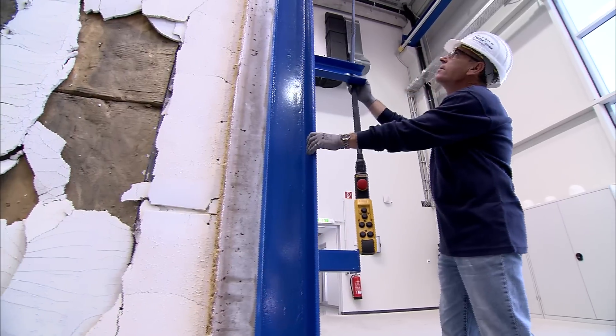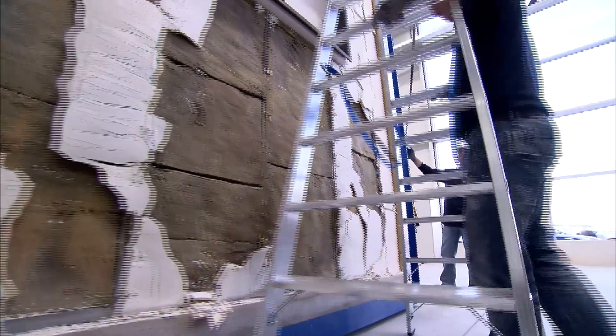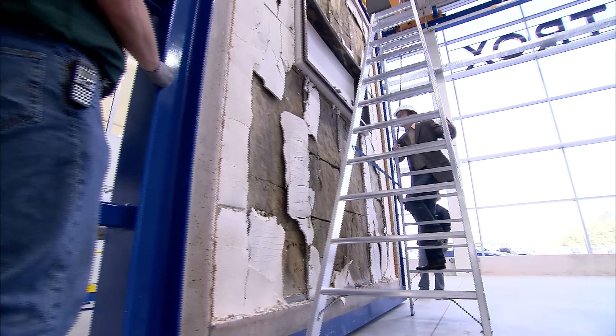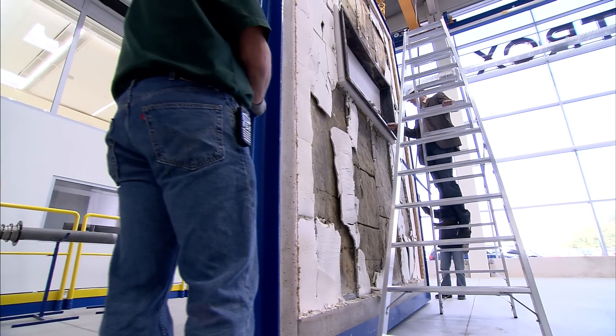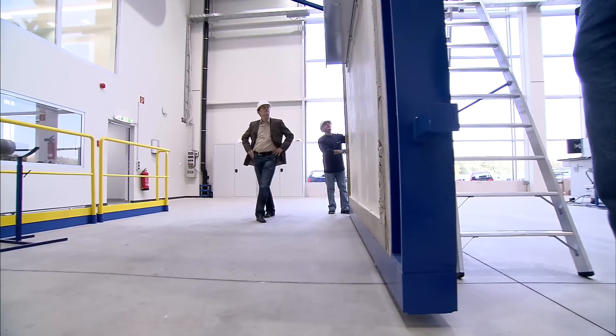The wall is badly damaged. The intense heat has discolored and deformed the metal parts of the damper, but it has passed the test with a score of 100% and maintained its seal. In real life, it could have saved many lives.